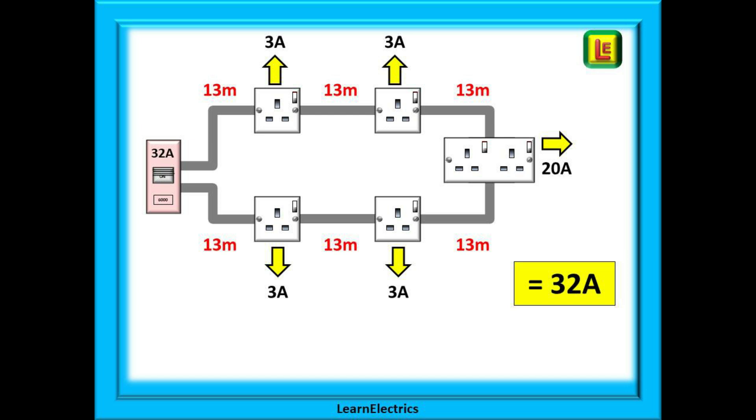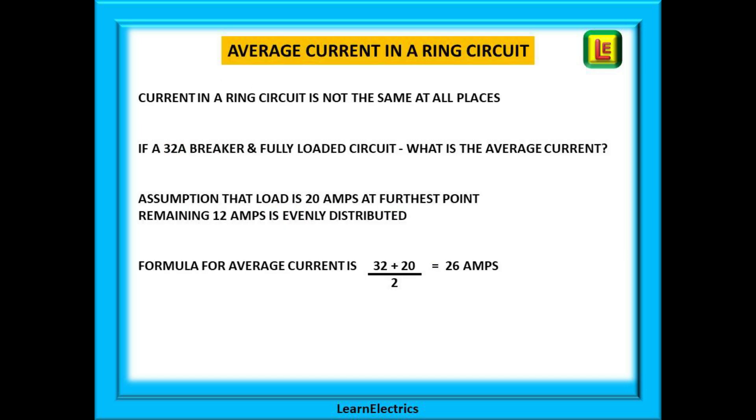If we add this up we have a total loading of 32 amps and this is our IB. But the design regulations permit us to make allowances for the fact that not every piece of cable will be fully loaded.